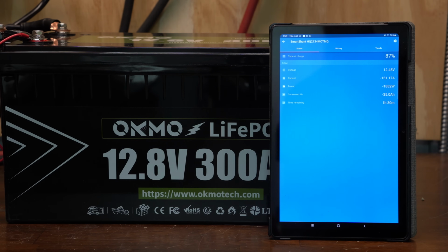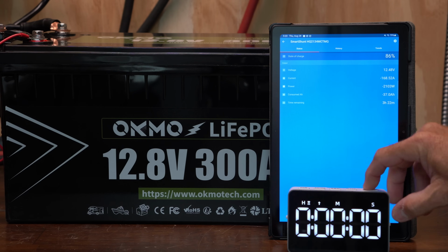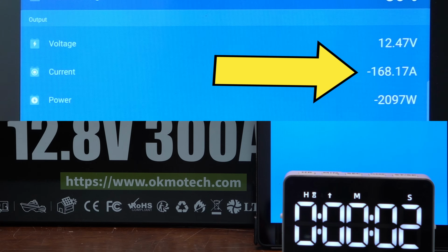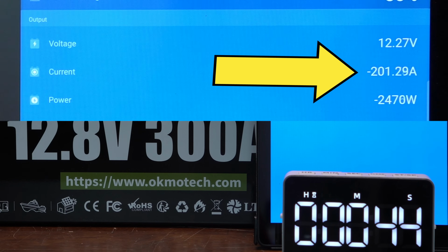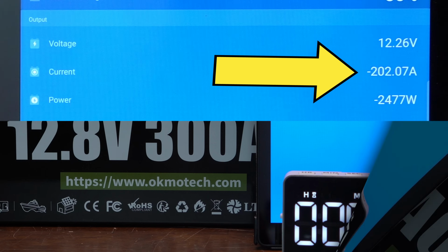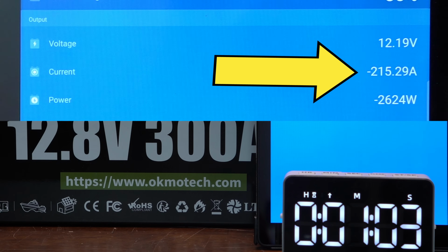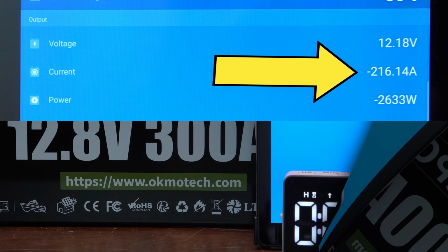Let's try and push this thing and see how far we can get it before the BMS actually shuts us down. I'll go ahead and put a timer up just so we can see how much time we're actually burning here. We're at 168 amps. So out of that rated 150 amp BMS, we're discharging at 201 amps. We're 1 minute in, and we are now at 215 amps.